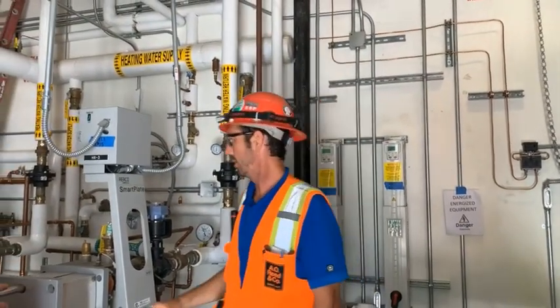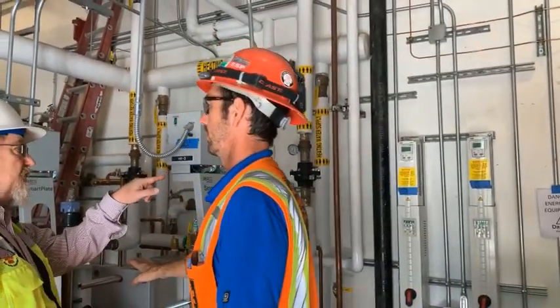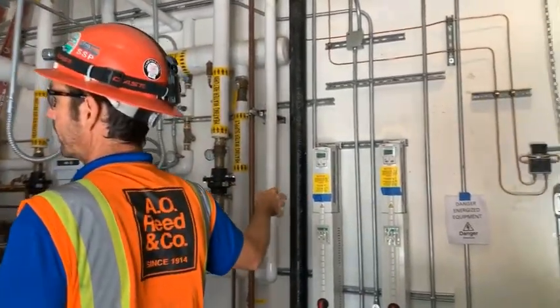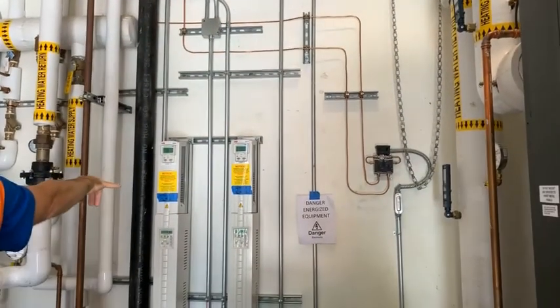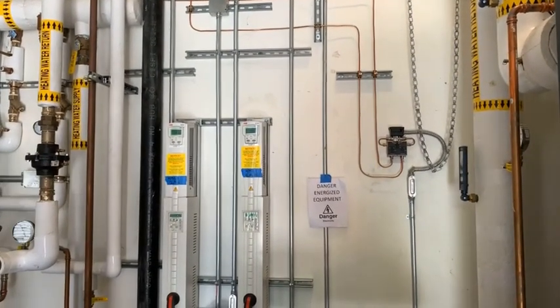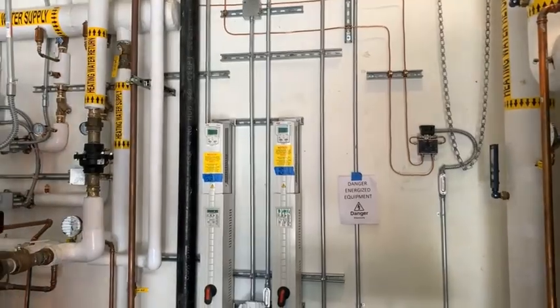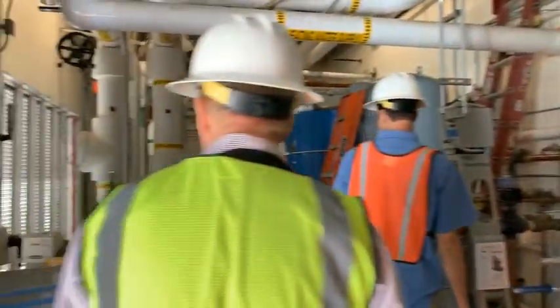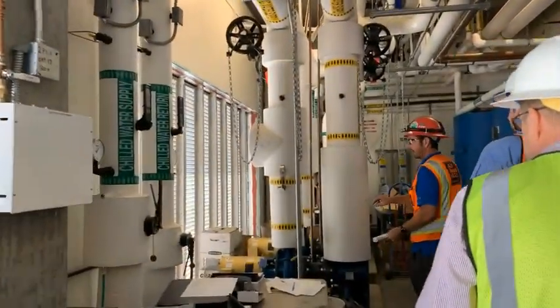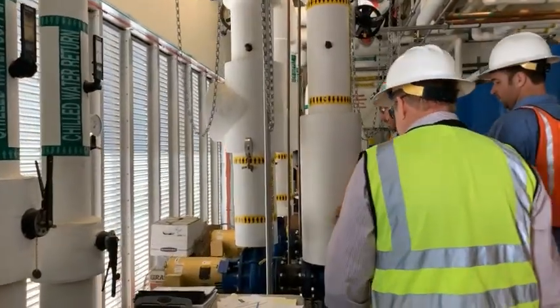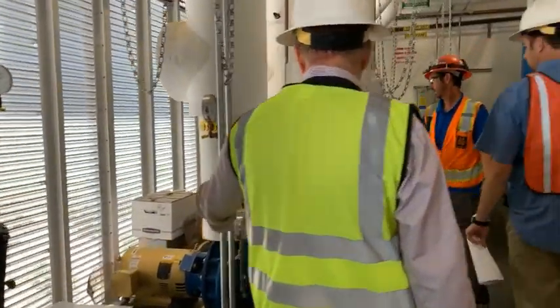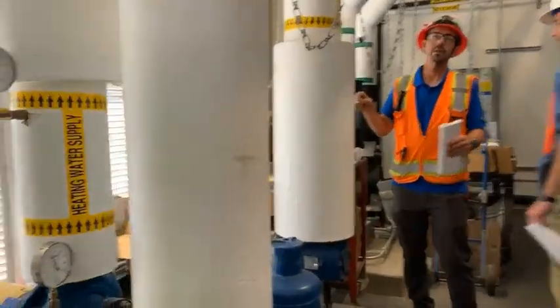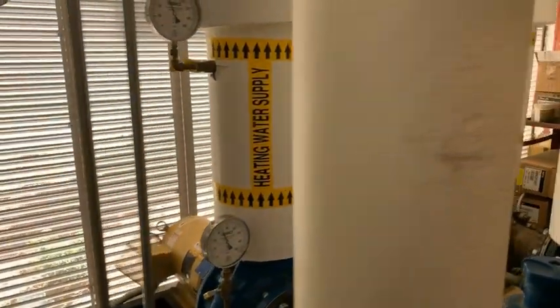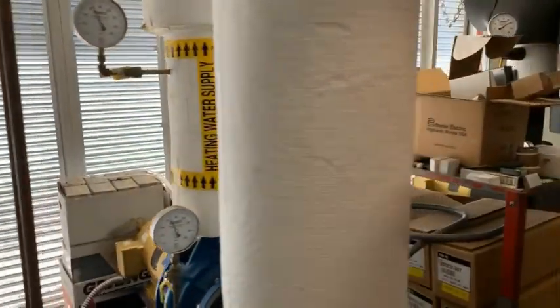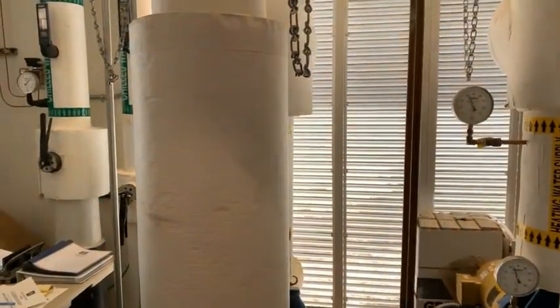Those two, aren't they one for each boiler? They're redundant. These are your building heating hot water pumps. So those are the ones we talked about over there. Over here, they're going to be these guys right here. So we have heating hot water pump 4 and 3, and these are circulating the heating hot water throughout the entire building and the heat exchangers. So if these pumps aren't running, we're not going to be pumping the 140 through the heat exchangers. They're not going to make their temperature.